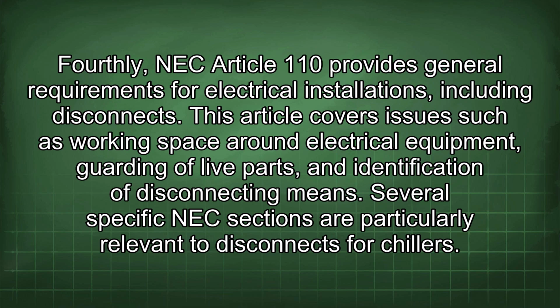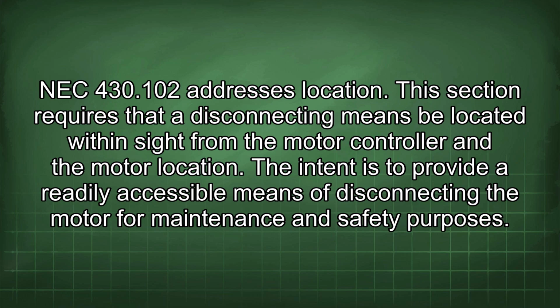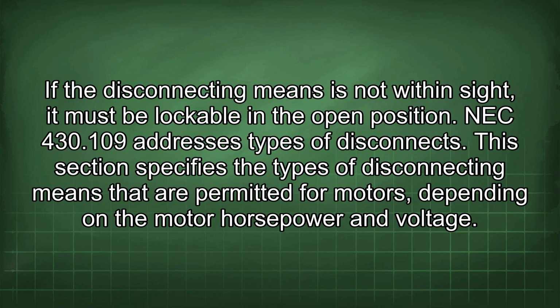Several specific NEC sections are particularly relevant to disconnects for chillers. NEC 430.102 addresses location. This section requires that a disconnecting means be located within sight from the motor controller and the motor location. The intent is to provide a readily accessible means of disconnecting the motor for maintenance and safety purposes. If the disconnecting means is not within sight, it must be lockable in the open position.